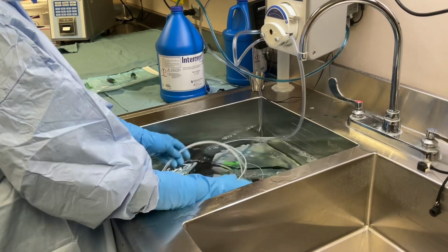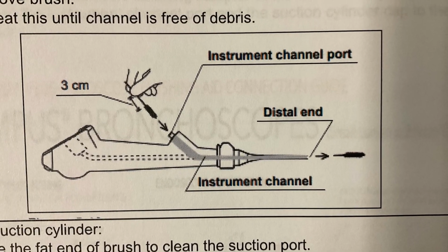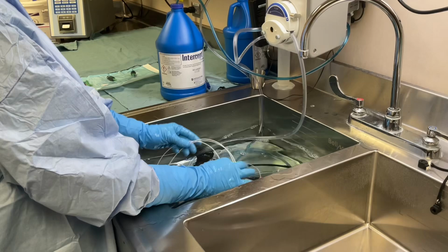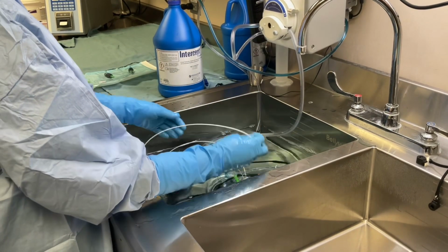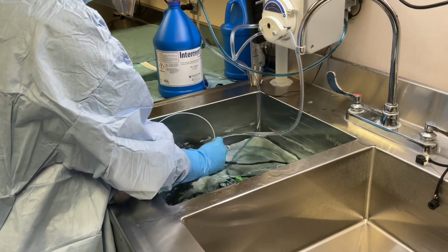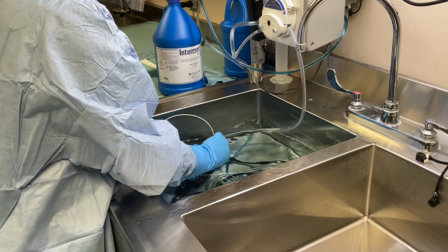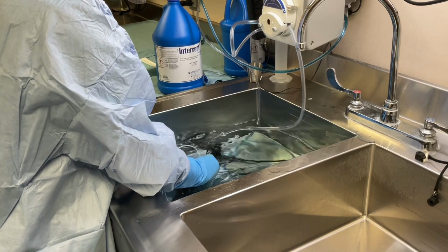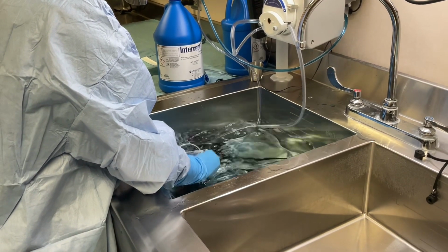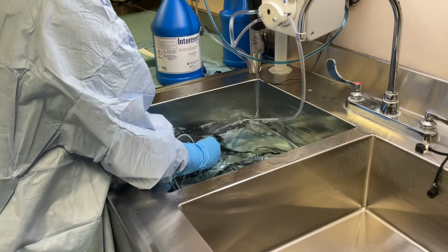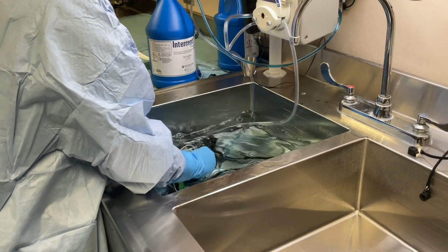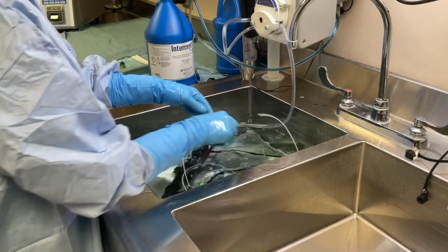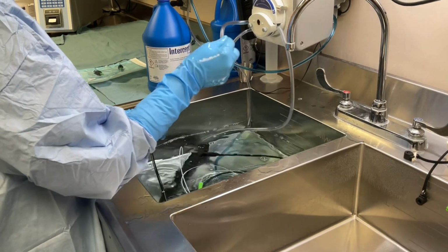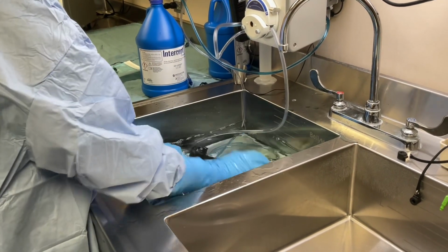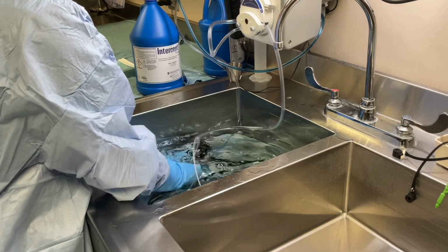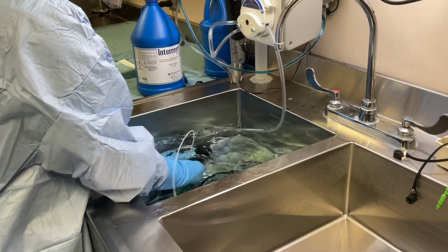Brushing instrument channel. While the endoscope is completely submerged, brush the instrument biopsy port channel. Using short strokes, pass the cleaning brush into the instrument channel until it emerges from the distal end of the endoscope. Observe the end and clean off debris. Remove the brush and repeat this until the channel is free of debris.